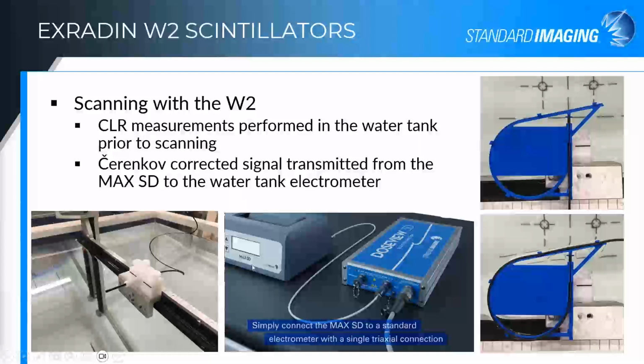That fiber then goes into the Max SD, which you've already previously calibrated or set up your CLR, or you can do it before you start scanning via its interface. It can then just operate in pass-through mode, where it gets the signal from the optical fiber, does the Cherenkov correction, and then outputs that proportional analog signal, the current, to your water tank scanning electrometer, like our DOSEVIEW 3D electrometer that's shown here.